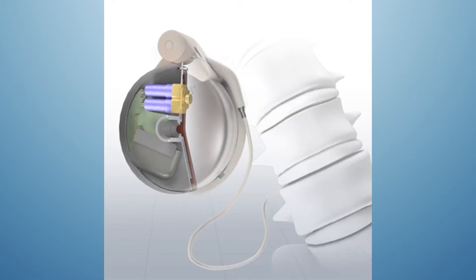This video is showing the Flow Onyx pump, which avoids problems that other pumps have had in the past. There's been fibrosis or scarring around the tips of the catheter, and that's interfered with the medicine delivery system in pain pumps in the past. But the way the Flow Onyx pump works — the one that I implant — helps avoid that kind of problem: the problem of fibrosis or scar formation along the tip of the catheter.